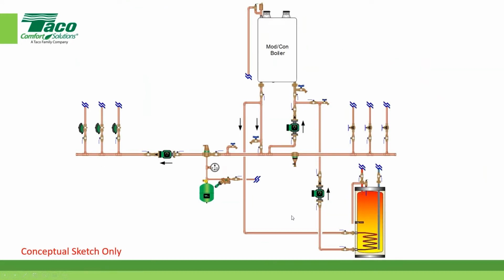Okay. So this is just like a wall hung Mod Con closely spaced T, so that we'll call that our primary secondary configuration. I like to say T's butted together. But let's look at zone 1 at 3 gallons a minute, zone 2 at 2.2, and zone 3 at 2. And these GPM numbers came from the loads based on those zones. Okay, so these are in this case hypothetical. But let's start with zone 1.